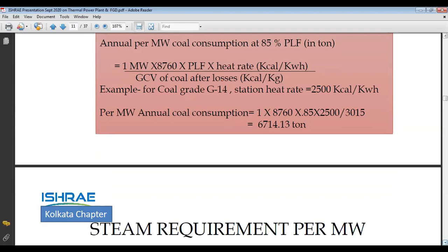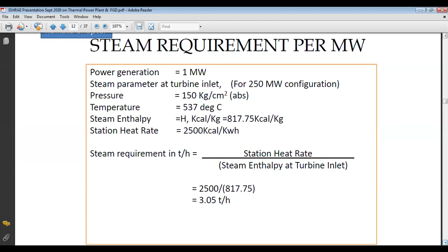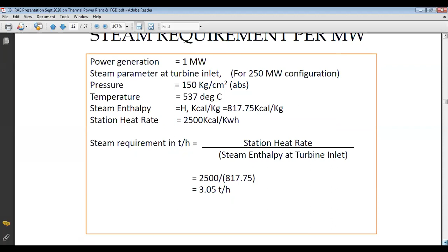Another thing is the steam requirement. Generally a question is asked, what will be the per megawatt steam requirement for a thermal power station. So generally, as a thumb rule, we utilize 4.2 or 4 tons per megawatt, but it varies from station to station, depending on the station heat rate. So, for example, I have given an example for this 250 megawatt configuration. Suppose the pressure and temperature for that configuration is 150 and 537 degrees centigrade. The enthalpy can be taken from the superheated zone from the steam table.